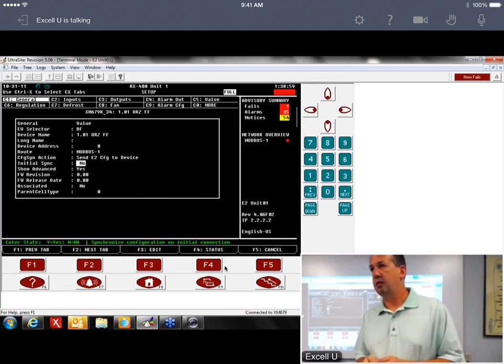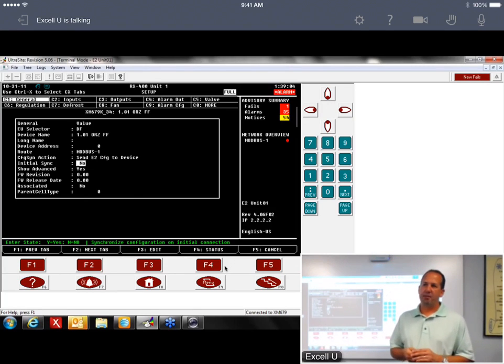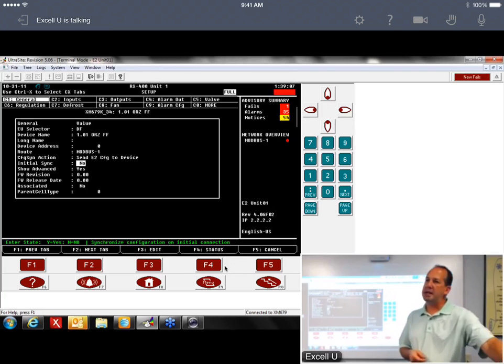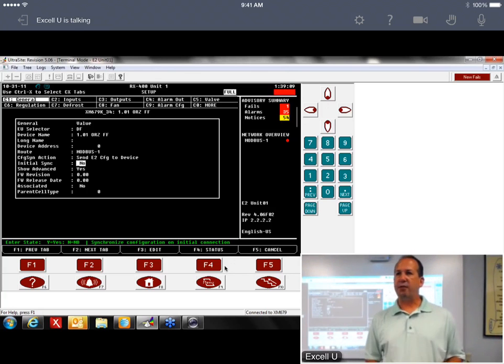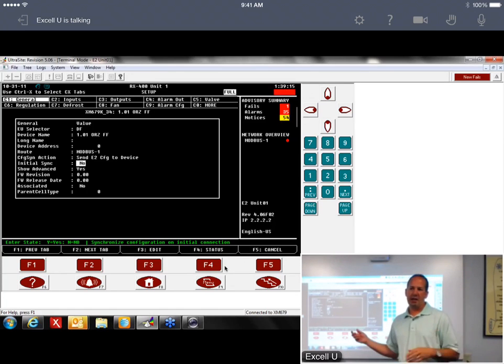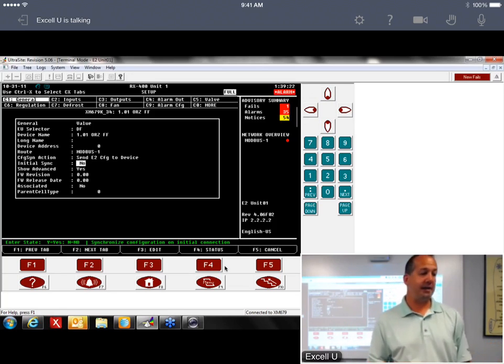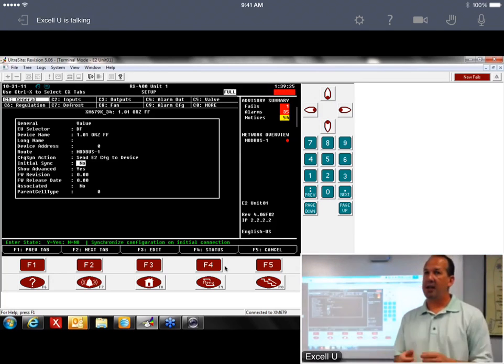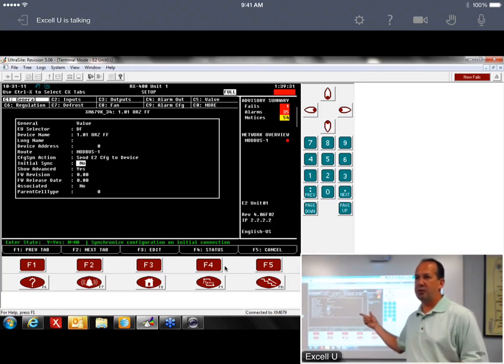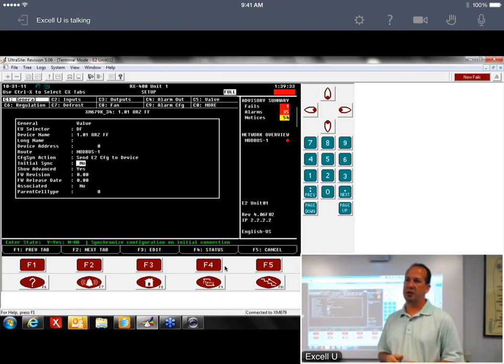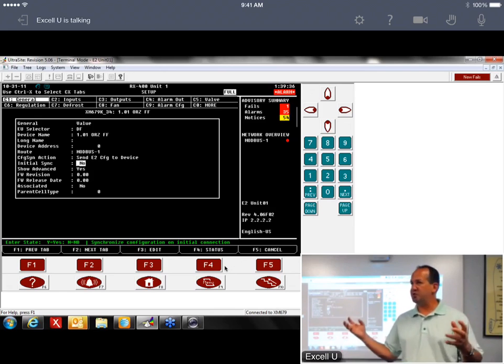Is that changeable to 4 or 6 times a day instead of twice a day? No, it's for the stores that lose power. It should be in there. So really what that's for is if you were to make a change in the E2 and didn't push the change down, it's going to catch that twice a day. So, or if somebody is monkeying around with this thing and changing stuff, changing the set point or something, twice a day when it goes through this, it's going to overwrite what was done there. So it just keeps the two the same.